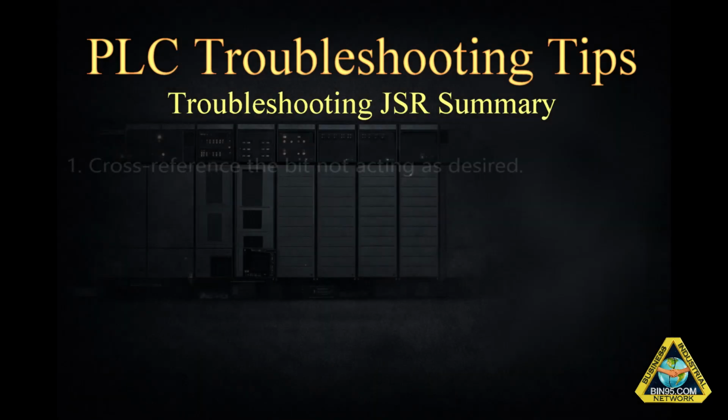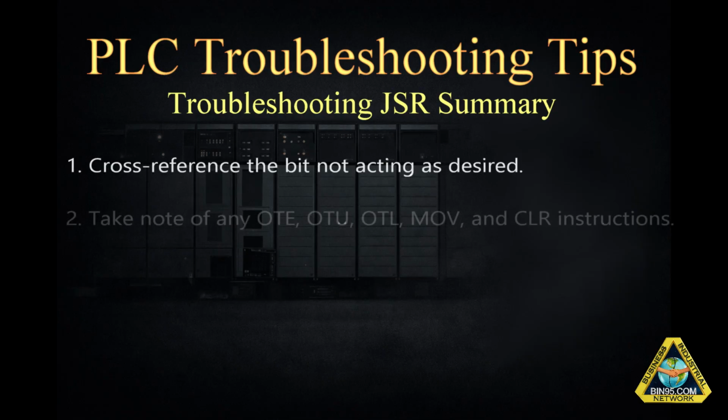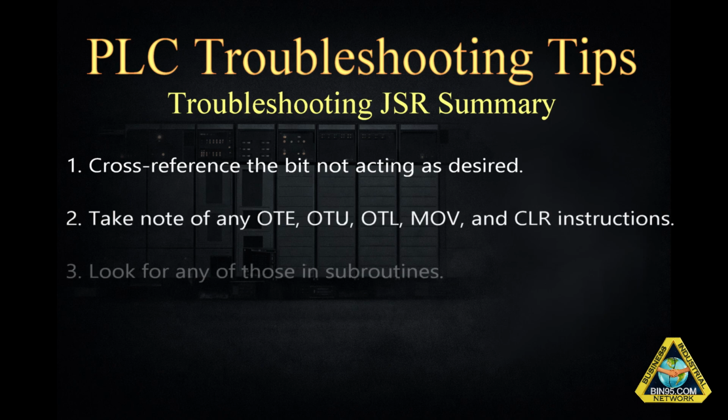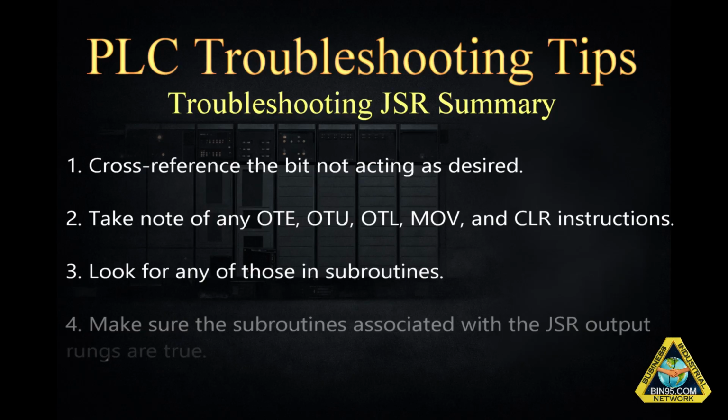Troubleshooting JSR issues is straightforward once you know the pattern. 1. Cross-reference the bit that's not behaving. 2. Look for OTE, OTU, OTL, MOV, and CLR instructions. 3. Check whether any of those are inside subroutines. 4. Verify that the JSR conditions for those subroutines are true.